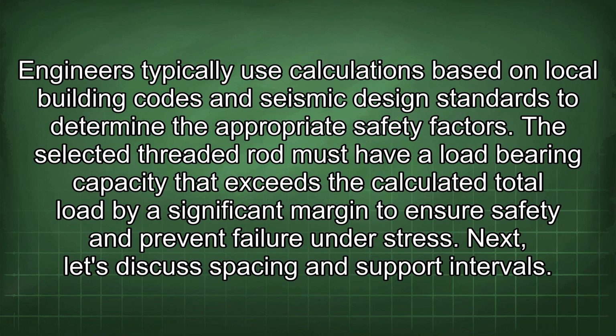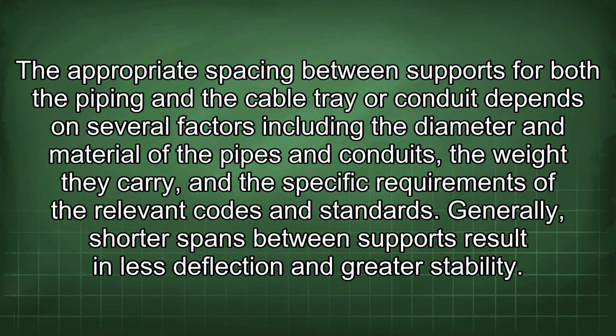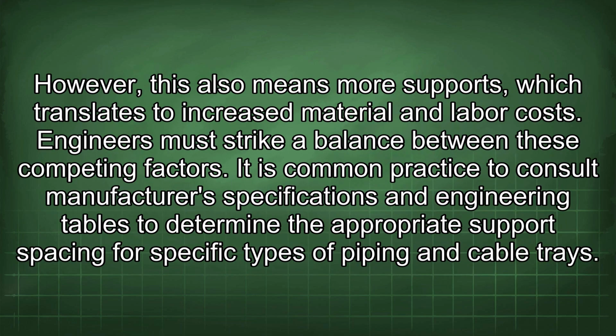Next, let's discuss spacing and support intervals. The appropriate spacing between supports for both the piping and the cable tray or conduit depends on several factors, including the diameter and material of the pipes and conduits, the weight they carry, and the specific requirements of the relevant codes and standards. Generally, shorter spans between supports result in less deflection and greater stability. However, this also means more supports, which translates to increased material and labor costs. Engineers must strike a balance between these competing factors.